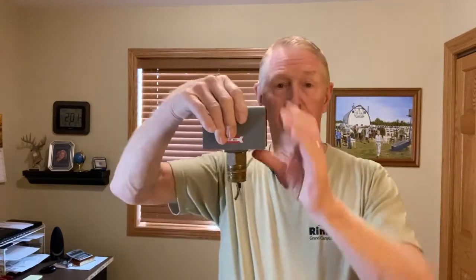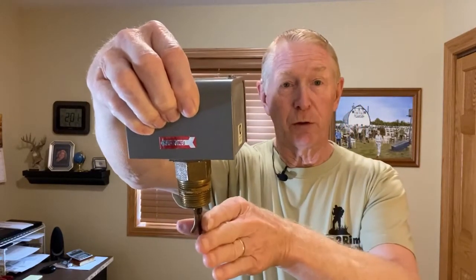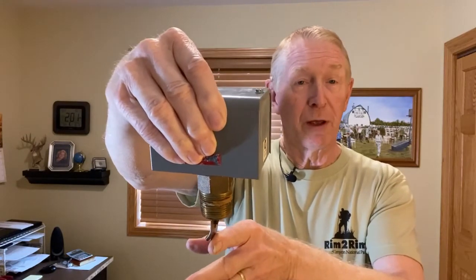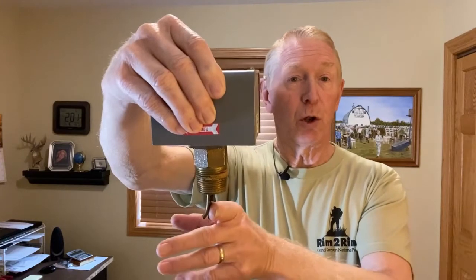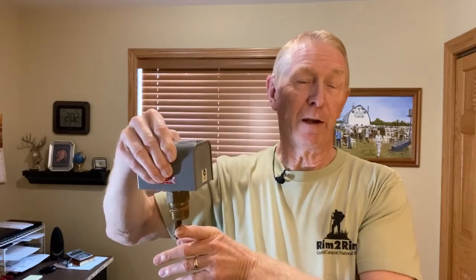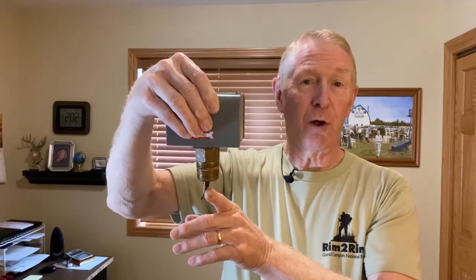The other type that's out there, and many newer boilers have these, condensing boilers will have these, is called a flow switch. The flow switch is piped down into the water line on the discharge side of the boiler, and as the water flows through the pipe, it will close. You can hear that. It will close the circuit and allow the fuel to burn in the burner. If the pumps were to stop and there was no flow, it opens and shuts off the burner. So this is another safety device that is used for low water control. So keep that in mind.